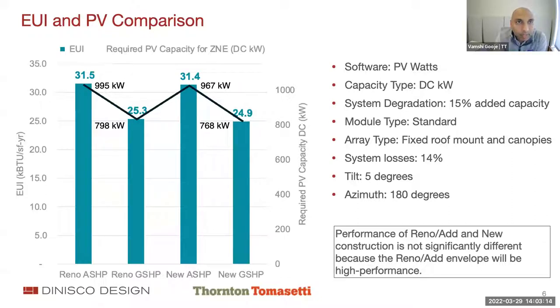That's correct. When we actually went back into the model and extracted the data, because we run these analyses on an hourly basis — for each hour, depending on whether it is a ground source heat pump, it will look at the incoming temperature of the water and how much load you have, and it calculates COP on an hourly basis. So when we ran the average COP for the year, we were close to 4 on the geothermal system, and then 2 COP for the air source heat pump system. So it is roughly — I'm not giving you any decimals.